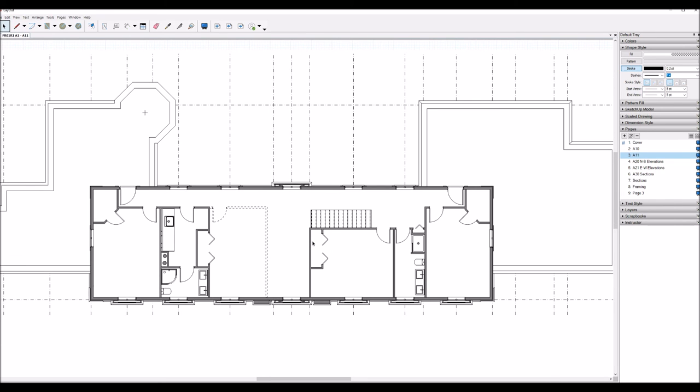And lastly, this house doesn't have a habitable attic, but it is insulated and there's enough space up there to be able to stand up and move around a little bit. I'm going to indicate a smoke detector and a carbon monoxide detector, and they will be placed near where the chimney penetrates through the attic. That way, if anything should start in the attic, the alarms will sound. When you're building a new house, all of these alarms are interconnected, so that if there's a detection in one place, all the alarms are activated so that everyone in the house knows about the danger. This is not always the case when you're retrofitting an existing house.